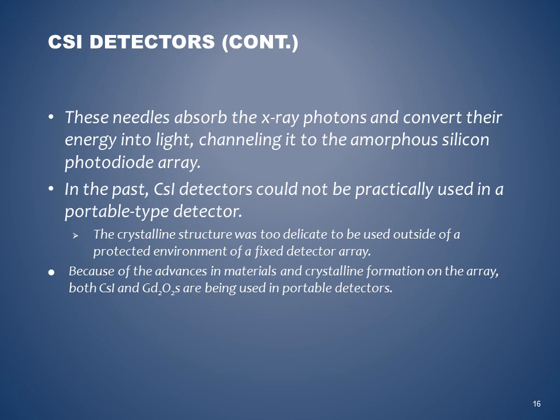CsI detectors. These needles absorb the X-ray photons and convert their energy into light, channeling it into an amorphous silicon photodiode array. In the past, CsI detectors could not be practically used in a portable type detector. The crystalline structure was too delicate to be used outside of the protected environment of a fixed detector array. Because of advances in materials and crystalline formation of the array, both CsI and Gd2O2S are being used in portable detectors.